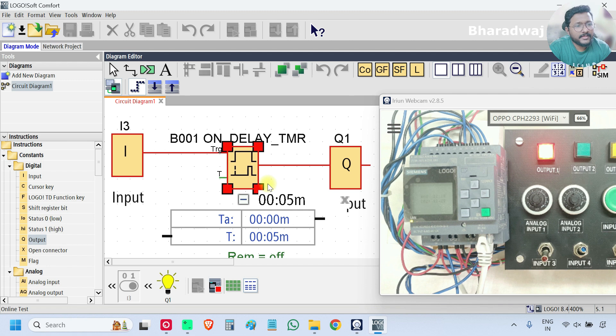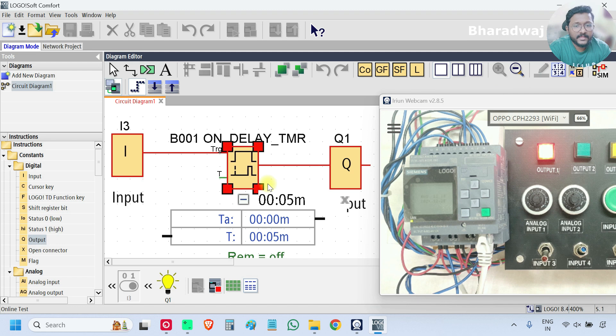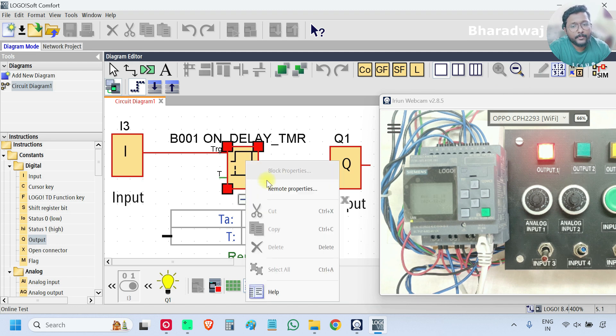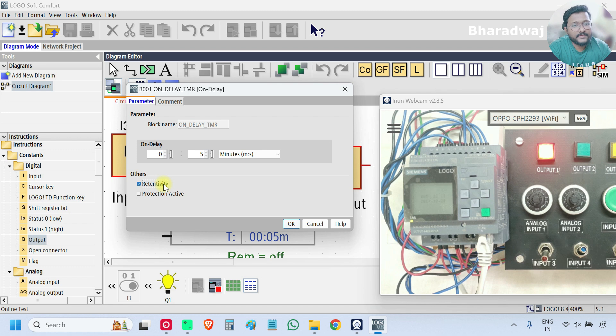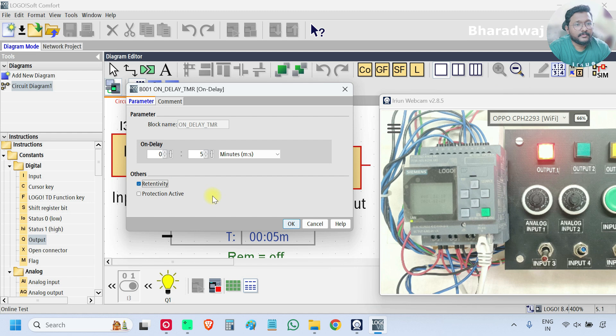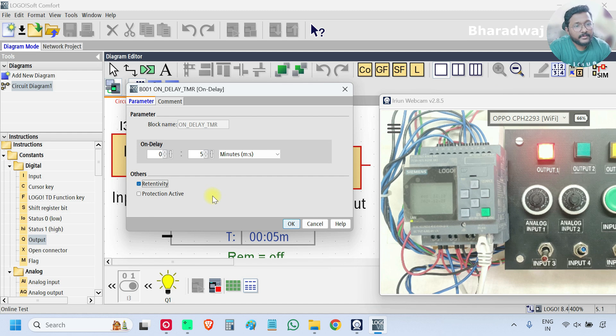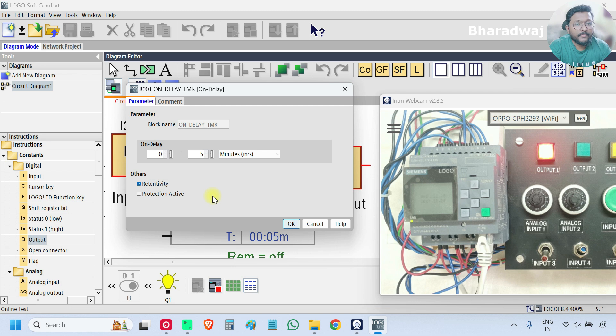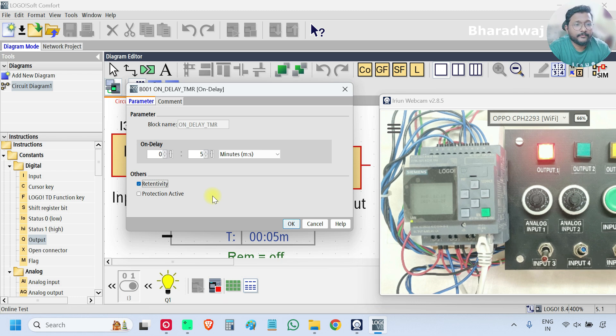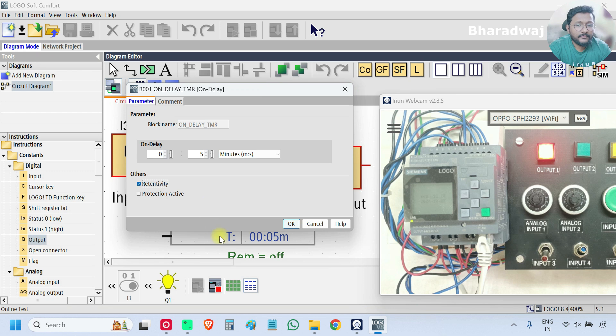So it will not save any previous data. But in some cases, some applications, you want to save the status. In this case, what you have to do, go to properties. And if you see one option is there, Retentivity. Select this one. For many blocks, you can find this retentivity option. That means that the specific block parameters can be saved during power off, PLC power off. Whenever it started again, it will continue from that previous state. Press ok.